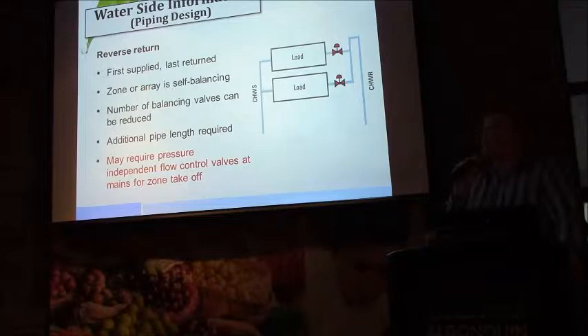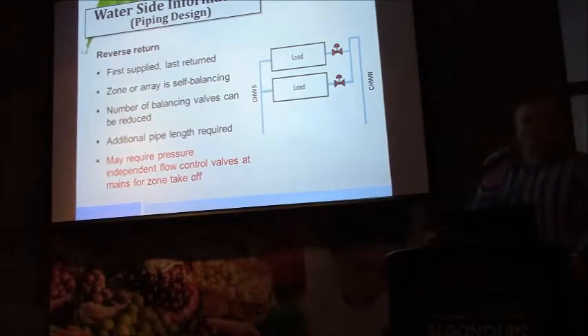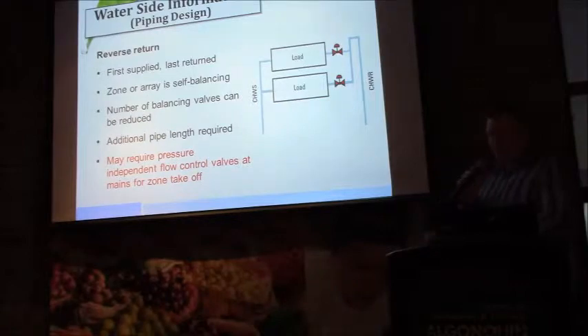And we're really designing closer to the bottom edge of what's required in terms of water flow to each beam. And so having any issue in terms of stable water flow is a problem. And so it's really pressure-independent flow regulating devices on the water that really solves those problems. They're very low cost as well.